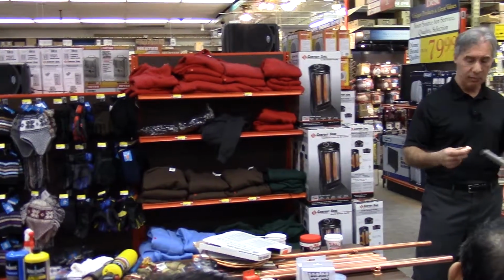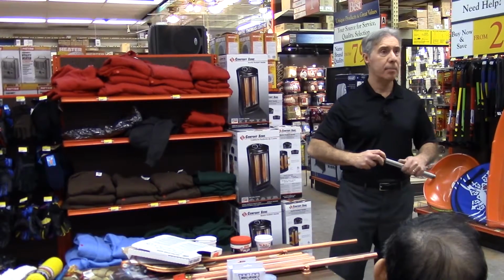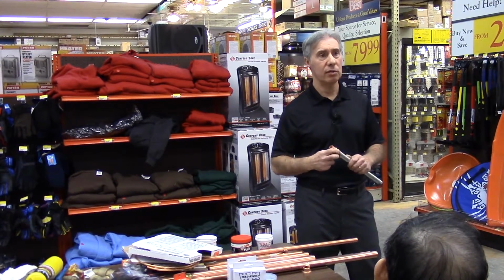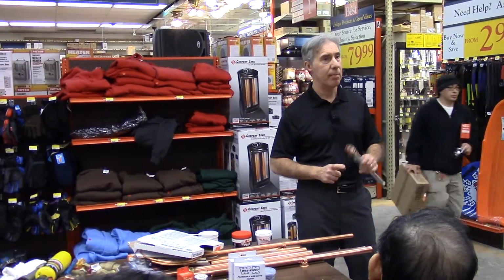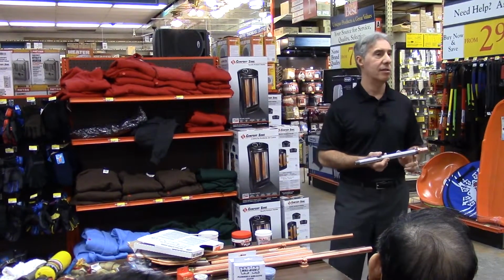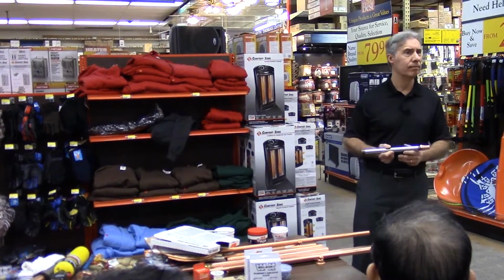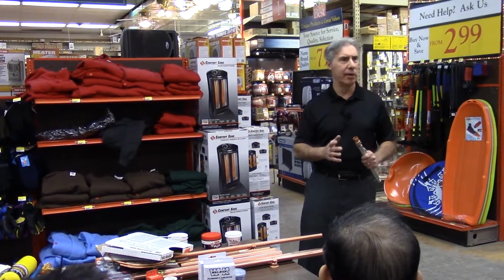When they are in direct contact with one another, what happens is you have electrolysis occur. That electrolysis does one of two things, or both things. It rots out and pits the copper pipe, and it rots out the threads on the galvanized. So there has to be a way to make that transition. And how do you make that transition between these two dissimilar metals?